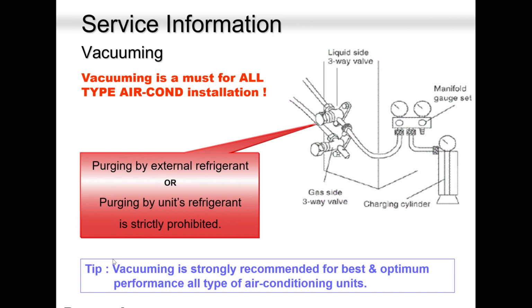As I mentioned earlier, don't purge using the internal refrigerant. Don't purge the system. Some people would do that. Please do not do it. Vacuum the system down to 300, even below. The lower you go, the better for you and me, and for the homeowner.